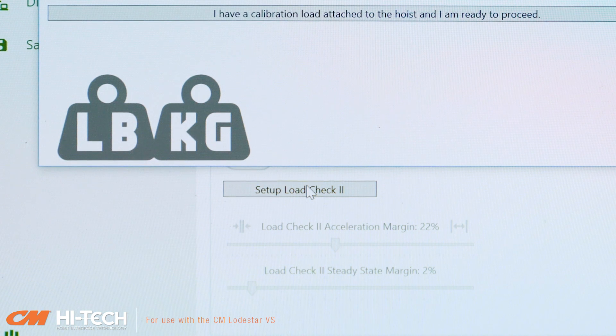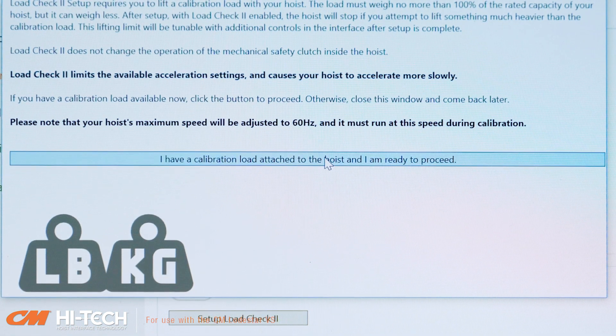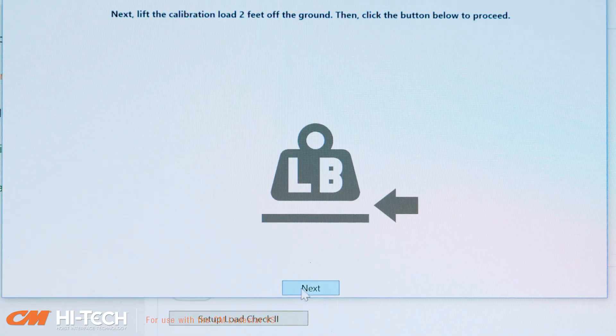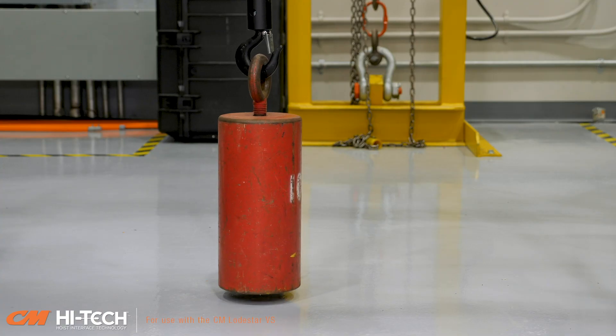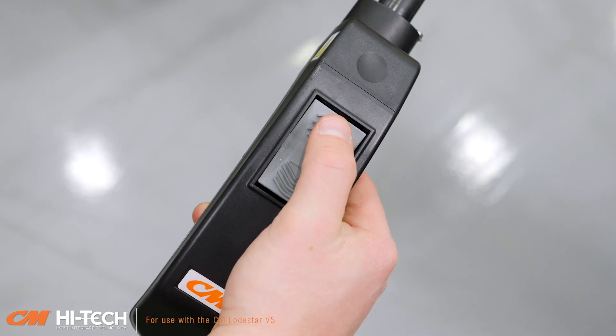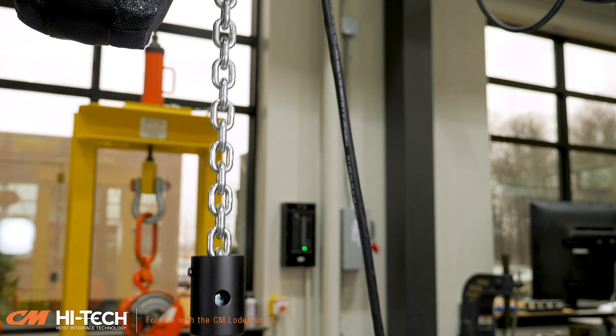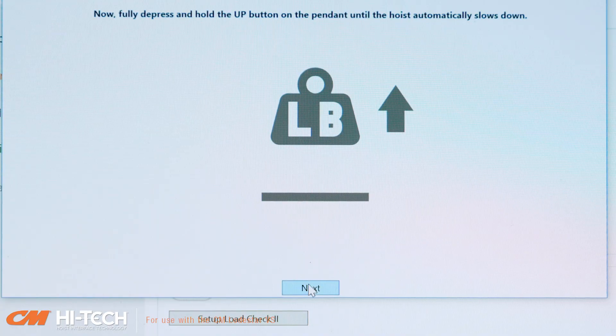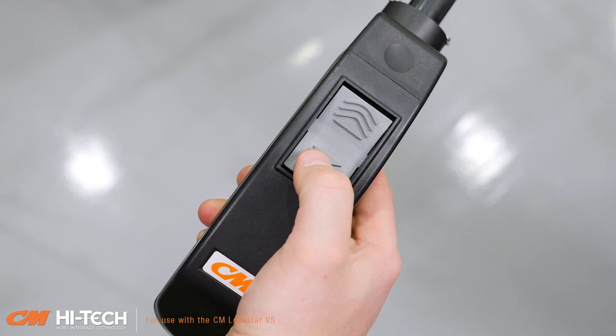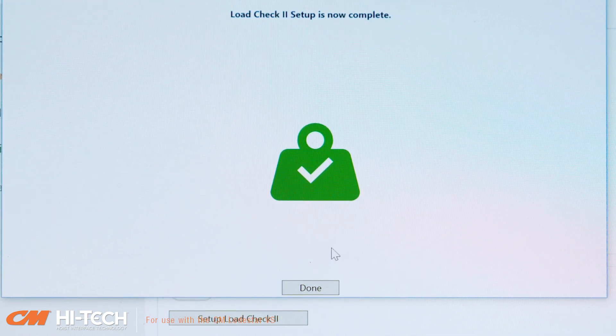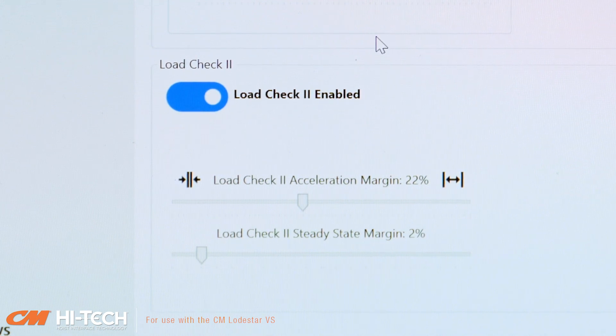Click on the Set Up Load Check 2 button, then read the calibration load requirements. If you have a calibration load available, attach it to the hoist and click the button to proceed. Lift the calibration load two feet off the ground, then click the next button to proceed. Fully depress the up button on your pendant until the hoist automatically slows down, then click the next button to proceed. Lower the load back to the ground and click the next button. Load Check 2 setup is now complete. Click the done button to return to the limits menu. You'll see Load Check 2 is now enabled.